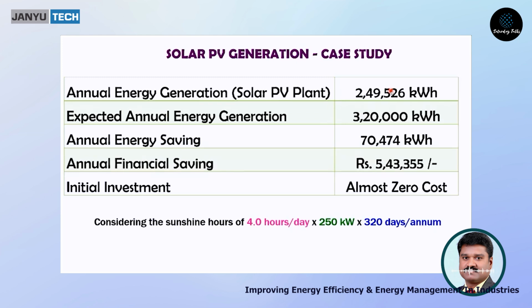Therefore, we recommended that you keep one inverter as a standby. You can link all the inverters with the help of a meter, and if any meter goes wrong, if any is not working, immediately the alarm will come. So automatically, the person in charge goes there and checks whether it can be rectified or not. If it is not rectified, replace it with the standby. Then you can put the system back to generation. So automatically you can save 70,000 kilowatt hours. If you convert that into a cost, it's going to be around 5.5 lakh, without investment.